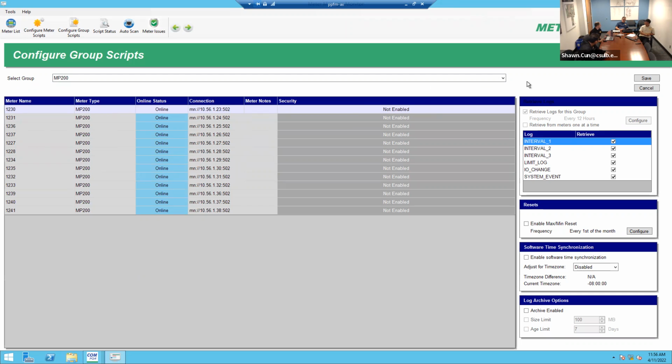Well, we would typically always use PQA, right? Yeah. And I'll get you the file there. You don't need to put in the key, because only the one that's on. Okay. Yeah, the remote computers don't necessarily need the professional mode, which has the meter manager, because that's basically just automating the download. And obviously, you don't want to do that from more than one computer anyway. But once it's downloaded, as long as you have access to that database or that folder or folders, then you can get to that data through COM PQA, pull up logs that have been downloaded and things like that.